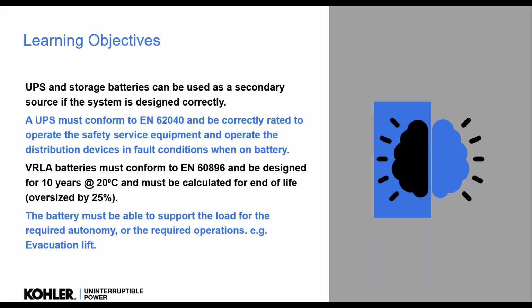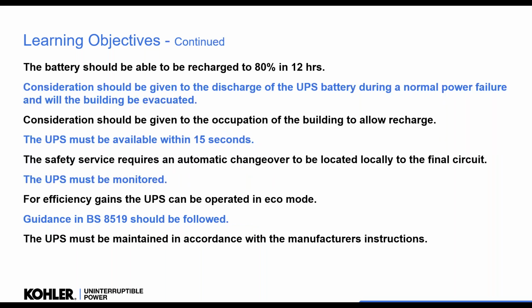Okay, or that might be the required number of operations, for example for an evacuation lift. Okay, and we know motors start and stop, and we have to size that battery accurately for that time. And again, not easy to do. We need to maybe have a lot of standby time before doing the autonomy at full load. And how you do that affects the size of the battery you put on. Okay. We should consider that we should be able to recharge the battery to 80% in 12 hours. Okay. We must consider that if we do tests in that building, we are going to discharge that battery, so we will not have the full autonomy, maybe, if required. So we should make consideration of that. When are we going to reoccupy?